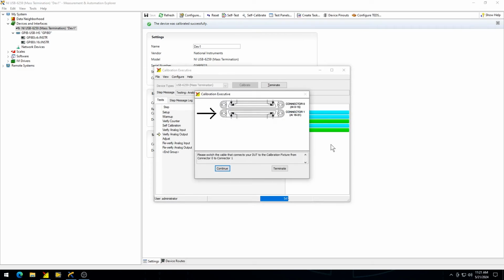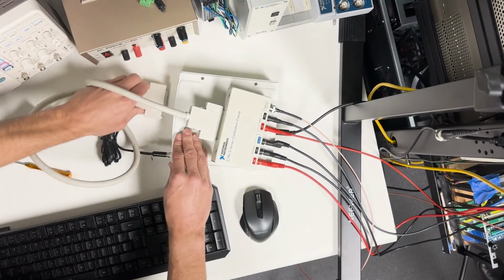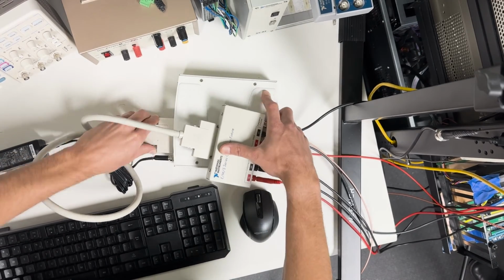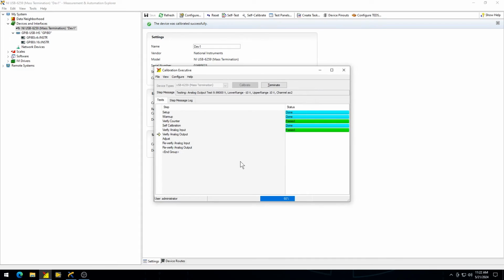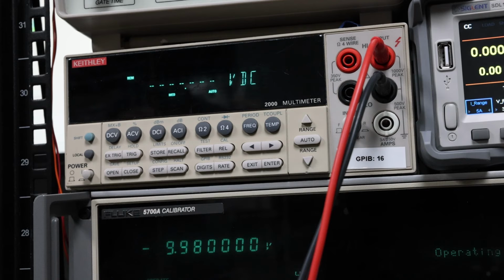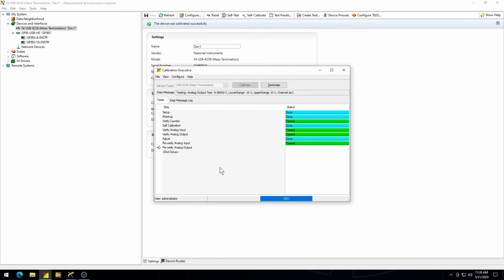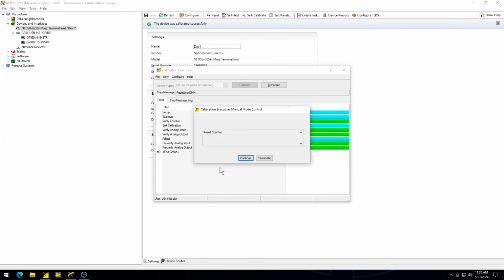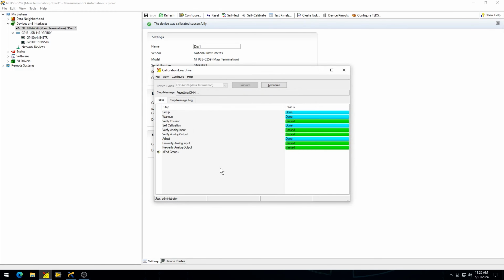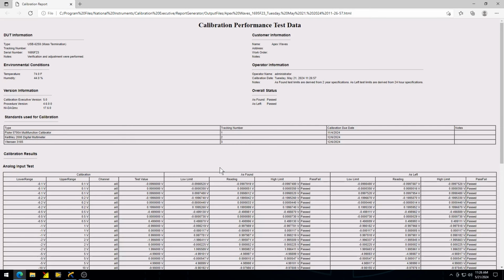Follow the instructions to switch the cable from connector 0 to connector 1 on the USB-6259 and click Continue. It will run another test of the verification of the analog input and output. Reset the counter when prompted. Finally, complete the calibration. If all steps are done correctly, you will receive a green notification stating Calibration Procedure Passed. Click Continue to access the Calibration Performance Test Data sheet.